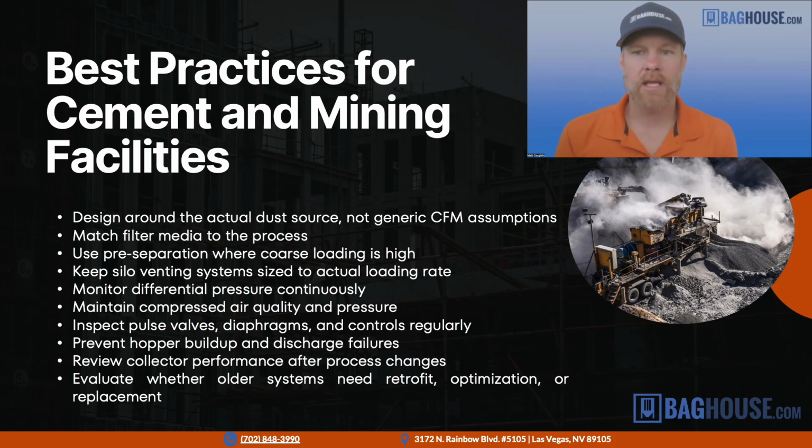Another thing to keep in mind here is that process changes are often unavoidable, but when your process does change and you move the equipment around, or you add something, or take something away, that may invalidate the original design basis for your dust collection system. So if you have an older system and it's not performing as it should, it's likely that some things have changed over time. The system balance is different. The processes connected to the dust collection system may have changed.